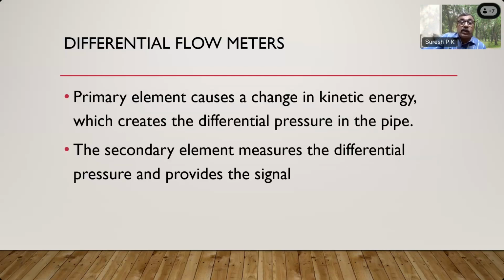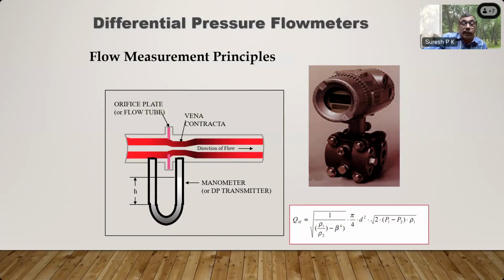The basic principle is that the primary element causes a change in kinetic energy, which creates a differential pressure. The differential pressure is induced in the flow by inserting a flow meter into the stream. The secondary element measures the differential pressure across the element, whose square root is proportional to the flow rate, or velocity rather. So this is the thing.